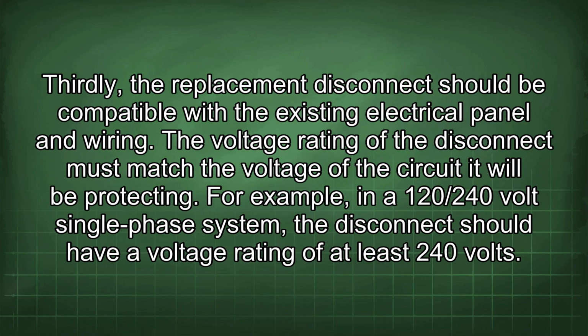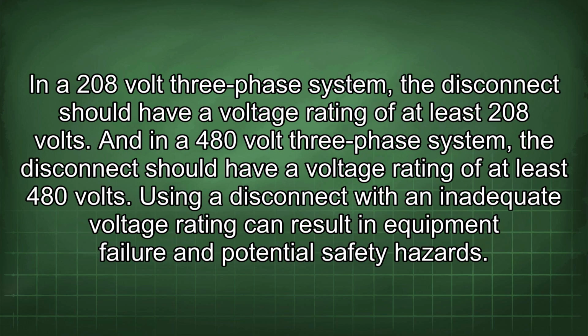The voltage rating of the disconnect must match the voltage of the circuit it will be protecting. For example, in a 120/240 volt single-phase system, the disconnect should have a voltage rating of at least 240 volts. In a 208 volt three-phase system, the disconnect should have a voltage rating of at least 208 volts. And in a 480 volt three-phase system, the disconnect should have a voltage rating of at least 480 volts. Using a disconnect with an inadequate voltage rating can result in equipment failure and potential safety hazards.